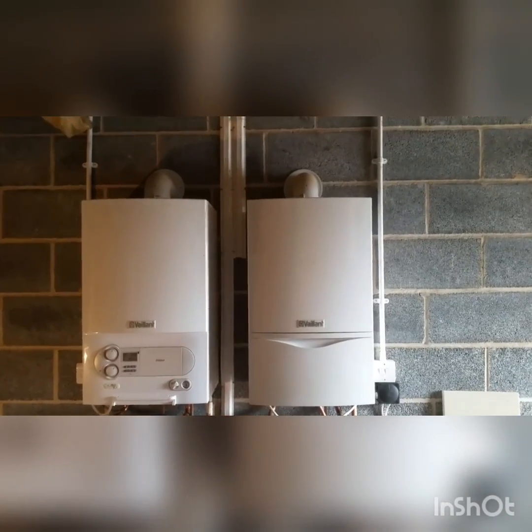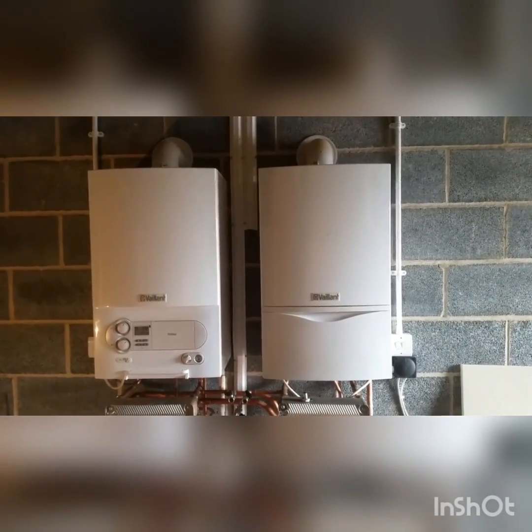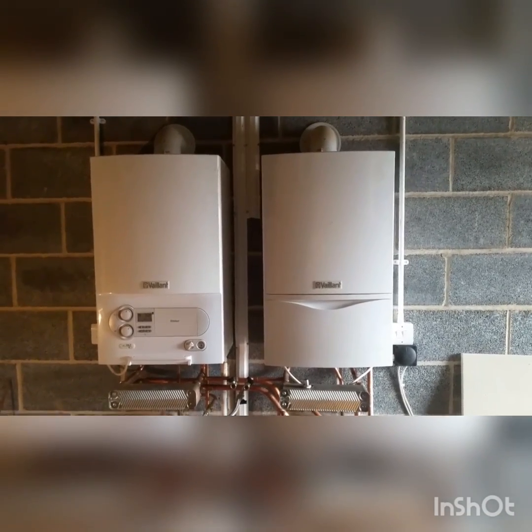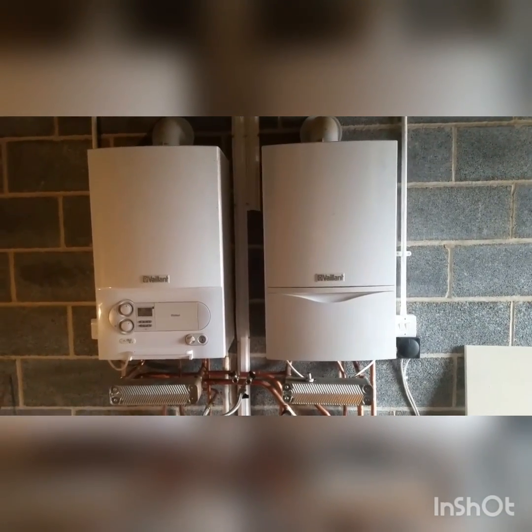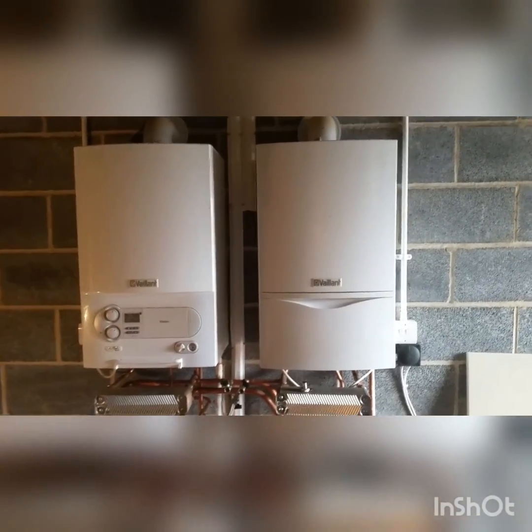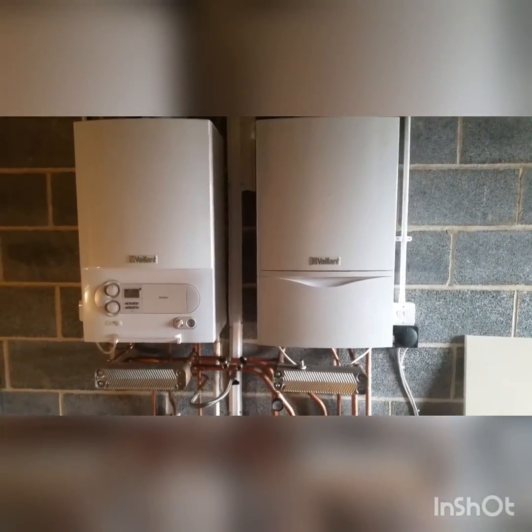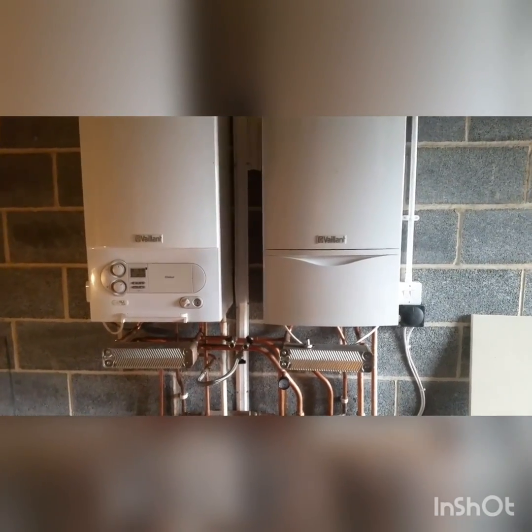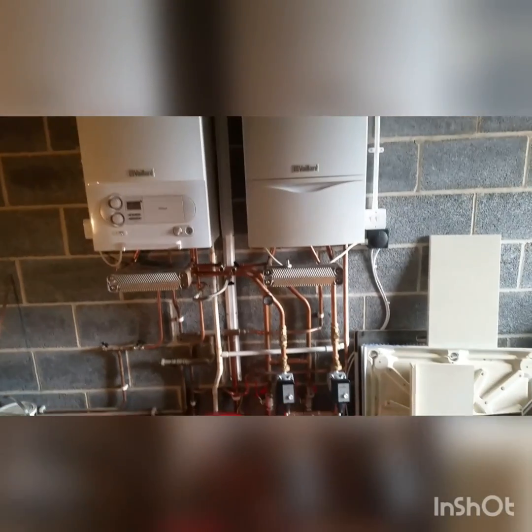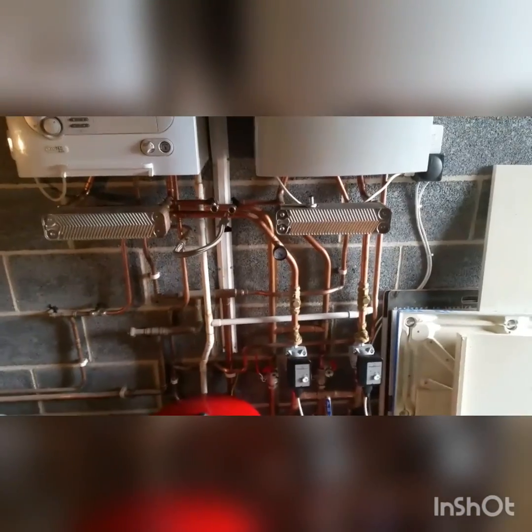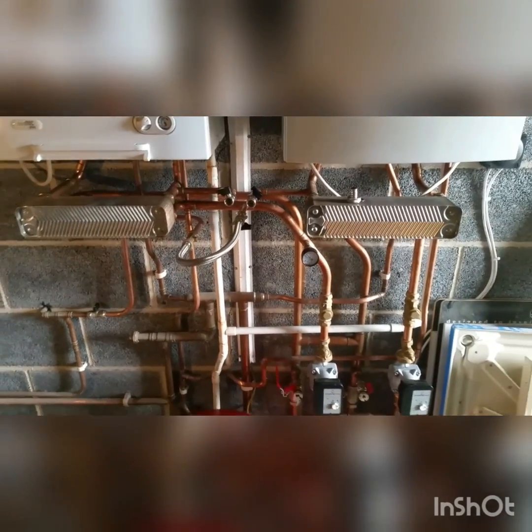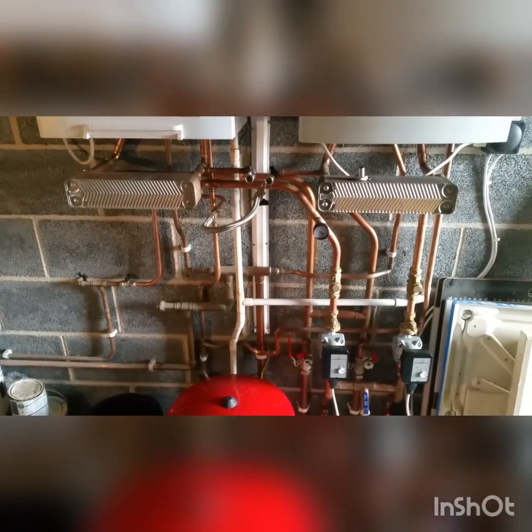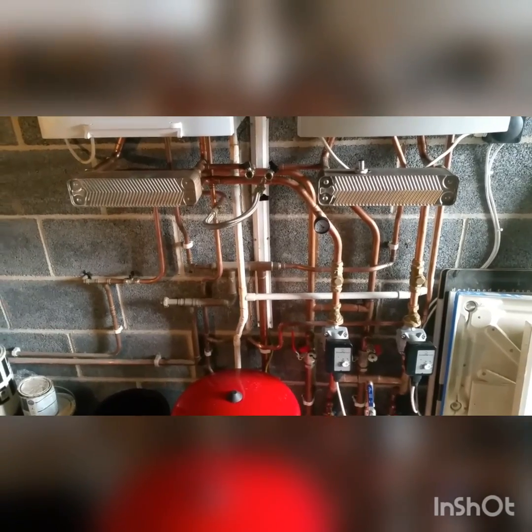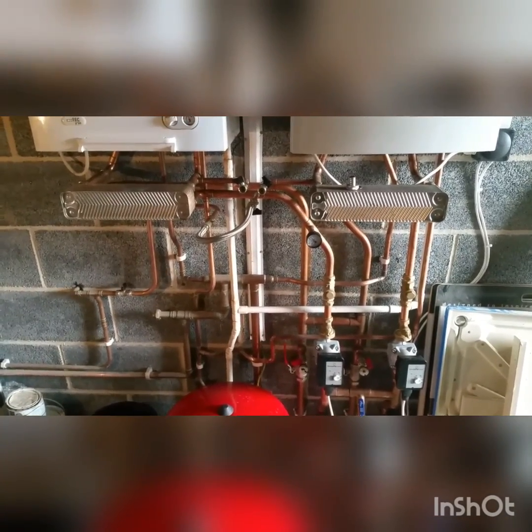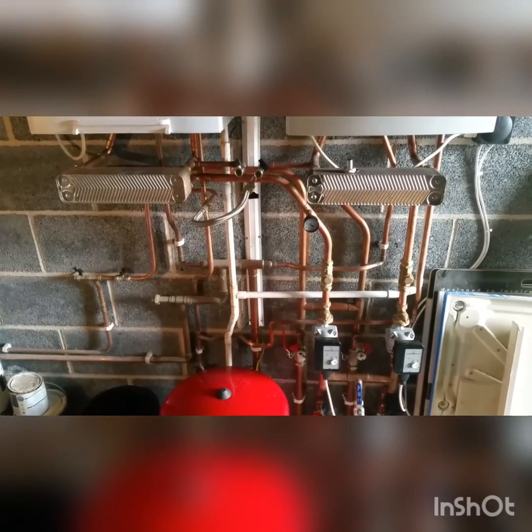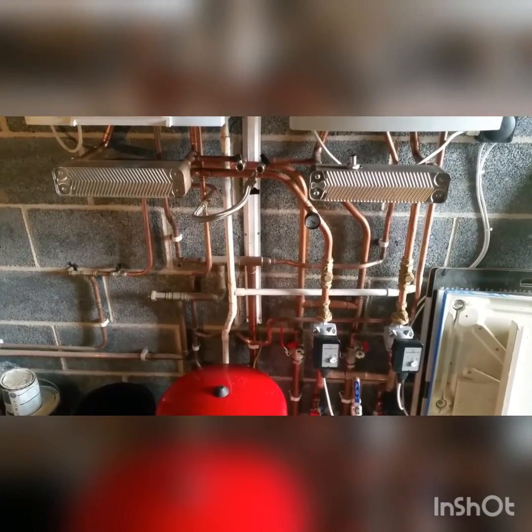Another job finished. Got called out to Vaillant system losing pressure, and found the failed heat exchanger. When I spoke to Vaillant, they intimated that the fact that there was no hydraulic separation on a pair of boilers may have contributed towards the failure of the heat exchanger. So I looked into the idea of a low loss header, but found that the underfloor heating system in the house here is all non-barrier pipe underfloor, and so requires plate separation according to, I think it's Viessmann's criteria.